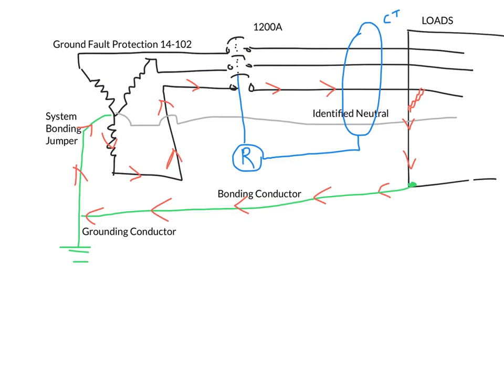Another option that works under similar circumstances is instead of putting the CT around the three phases and the neutral, we instead put the CT around the system bonding jumper. Under normal circumstances, that system bonding jumper should not be carrying fault current. But when a fault develops, fault current does flow through the system bonding jumper. So similar idea, the CT sees that current's flowing in a place that it's not supposed to. It senses that change and sends a signal to a relay, which in turn opens up the circuit.